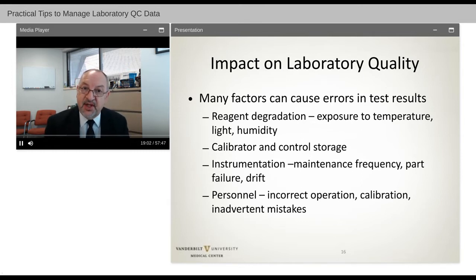Instrument maintenance is important to keep up daily, weekly, monthly, periodic, semi-annual, and annual maintenance needs to be done as specified by the manufacturer in their instructions for use, but also if you have a very high volume throughput of specimen samples, you may need to up the frequency of your maintenance because you may see wear and tear and failure of parts before the manufacturer recommended maintenance cycle. Personnel, we have to think about training, competency. Are they operating the analyzer correctly, and are they making inadvertent mistakes? How can we prevent those in the training process?